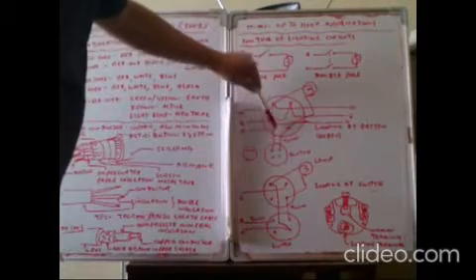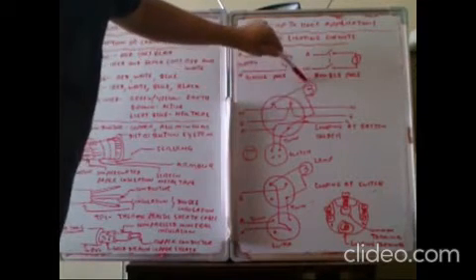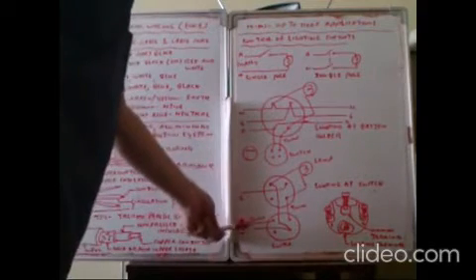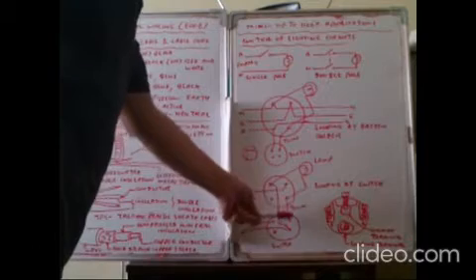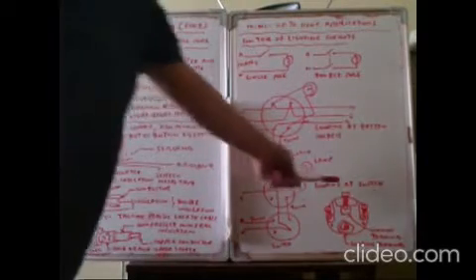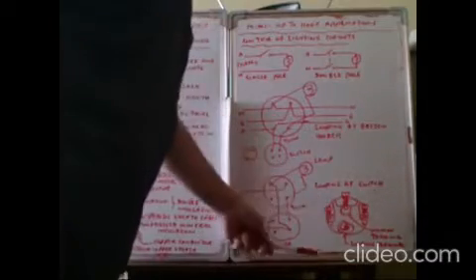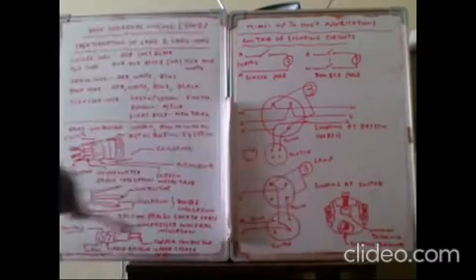In the wiring layout, the active wire goes to the switch and then to the light fitting. The neutral wire goes directly to the light fitting. Looping occurs at the ceiling rose and at the switch. The active wire is switched off at the switch. A two-way switch has three terminals: a common terminal and two light terminals. You can see these terminals at the back of the switch.